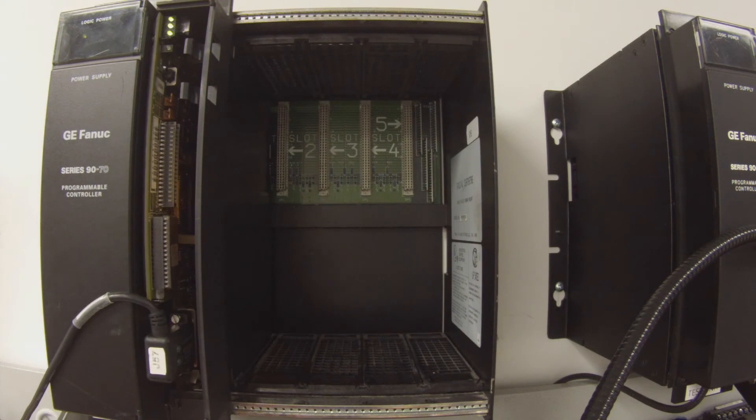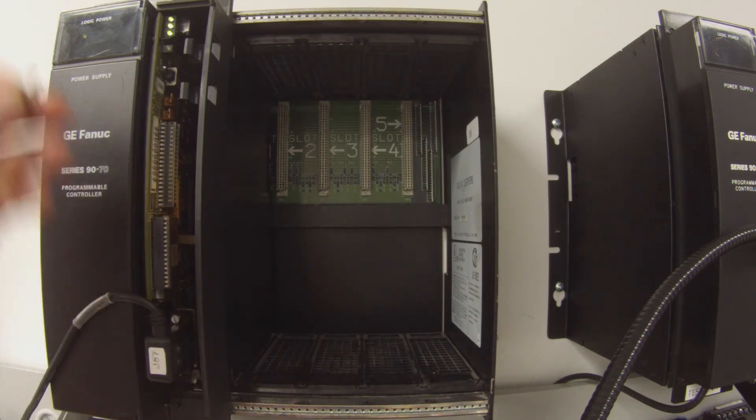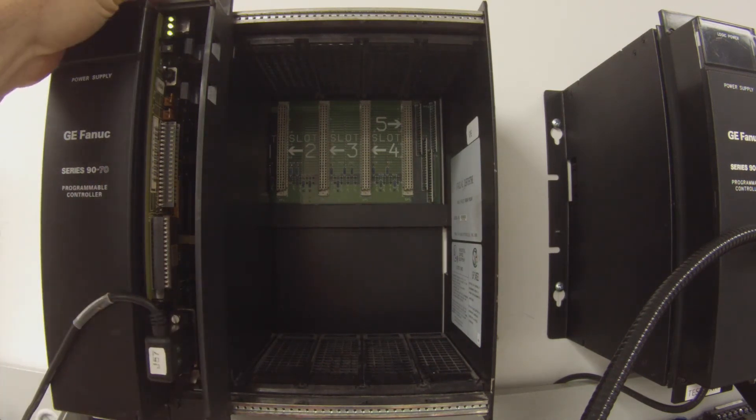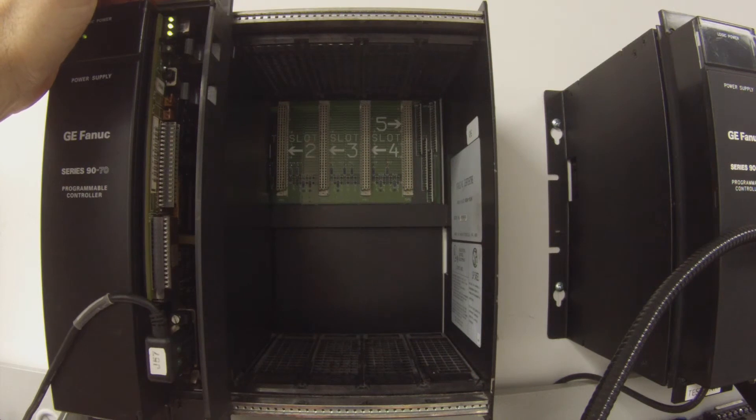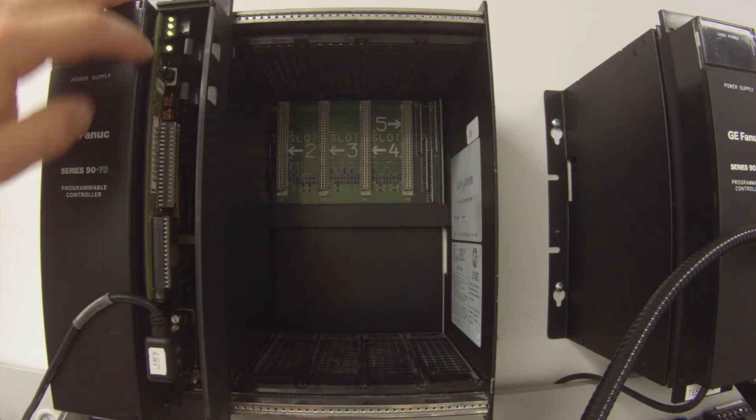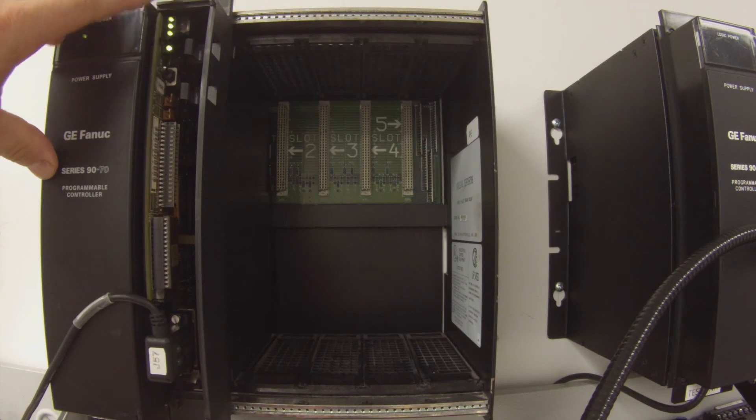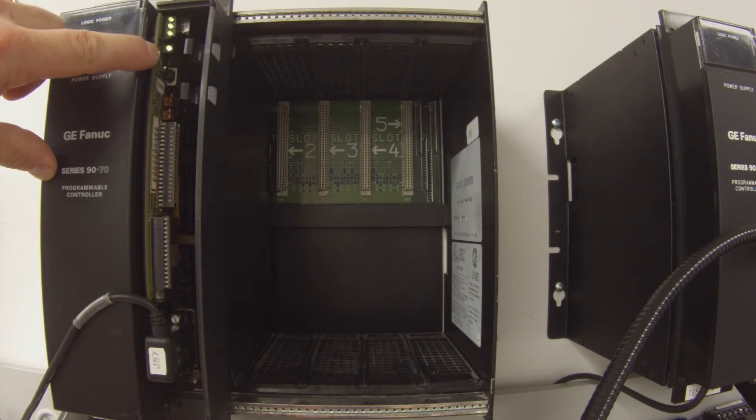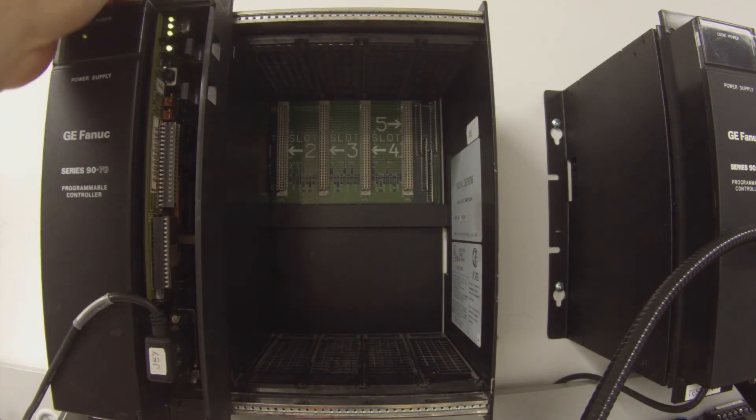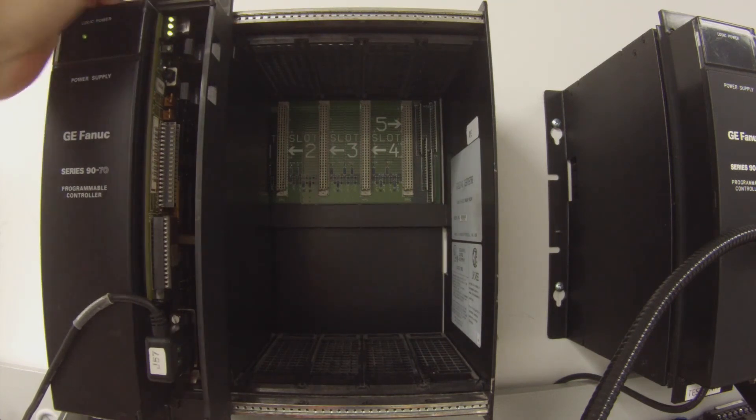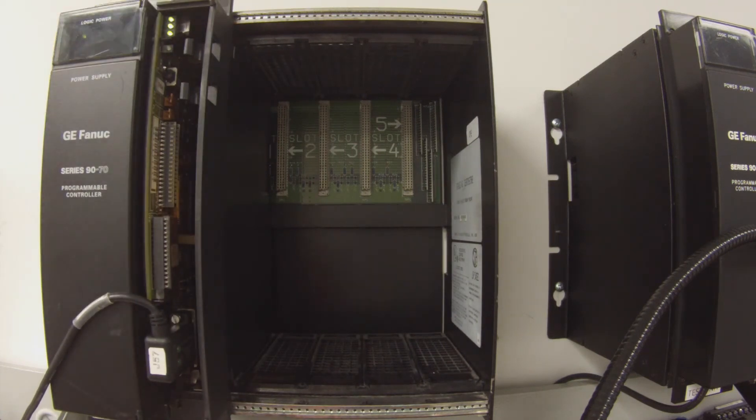Next thing of course is we have a key here, everybody knows the memory protect switch. This isn't always, sometimes we have a problem with it, it is not always an internal problem. A lot of times the switch will stop working. So ours is working and we can tell because when we turn it to the on position we have the memory protect LED turns on to tell us that that is functioning. That is good and we shut that back off. So I am okay with that.